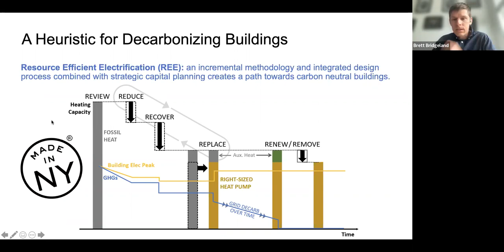Quickly, to highlight the importance of thermal recovery, heat recovery, and storage: what we found working with some properties is that office buildings, particularly in cold climates like New York City, still have significant cooling loads for a big chunk of the heating season. The approach in recent decades has been so-called free cooling at those times, taking advantage of cold outdoor air to cool spaces without running a chiller or other compressor-based system.